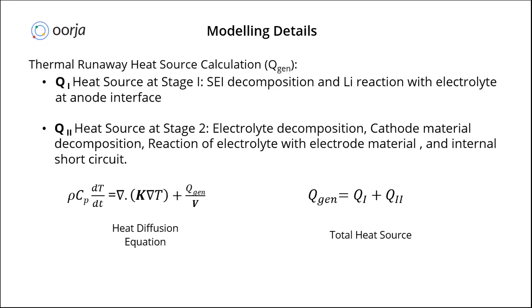So with that, once we start building the model, we can first try to understand how well we are capturing the thermal runaway signature of the cell itself, wherein you can see this is the ARC data we have used as an input to the model. In the pack level analysis, we can also accurately capture the onset of the thermal runaway. As and when the cell hits the T2 temperature, the stage 2 reactions also start, and because of that the accelerated heating starts happening inside the cell itself. Not just the onset of thermal runaway and the triggering temperature, we also capture the gas venting during thermal runaway.